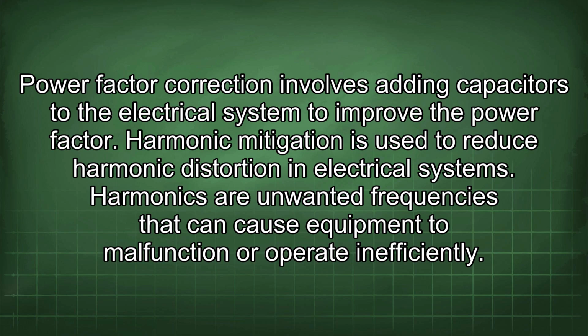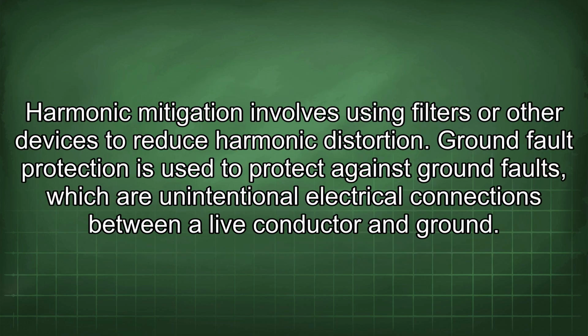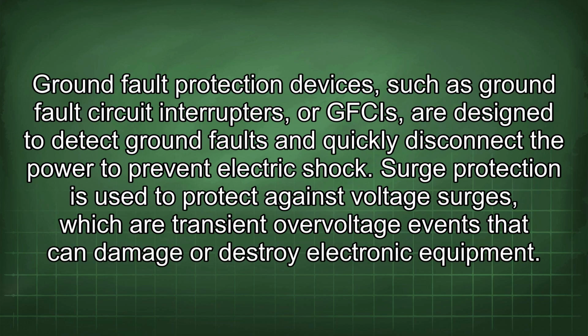Harmonic mitigation is used to reduce harmonic distortion in electrical systems. Harmonics are unwanted frequencies that can cause equipment to malfunction or operate inefficiently. Harmonic mitigation involves using filters or other devices to reduce harmonic distortion. Ground fault protection is used to protect against ground faults, which are unintentional electrical connections between a live conductor and ground. Ground fault protection devices, such as ground fault circuit interrupters, or GFCIs, are designed to detect ground faults and quickly disconnect the power to prevent electric shock.